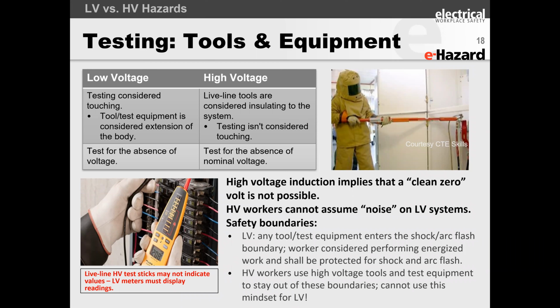However, at high voltage the approach is different. When using a live line tool, like you see in the top right picture, a person is not considered to be touching when testing, because they are trying to stay outside the minimum approach distance. The minimum approach distance for high voltage and low voltage are completely different. At higher voltage, live line tools are considered to insulate you from the system, so testing isn't considered touching.